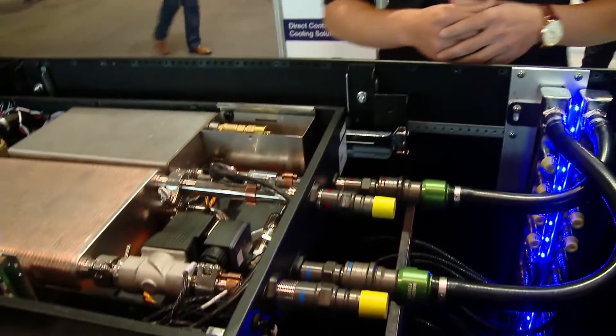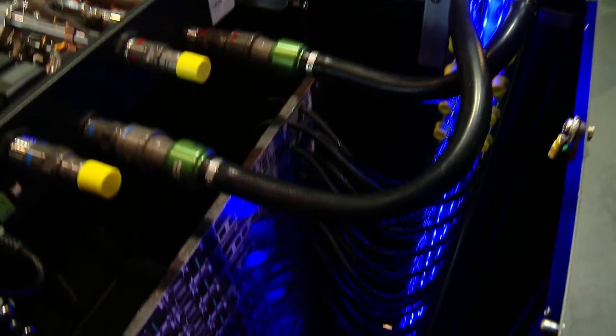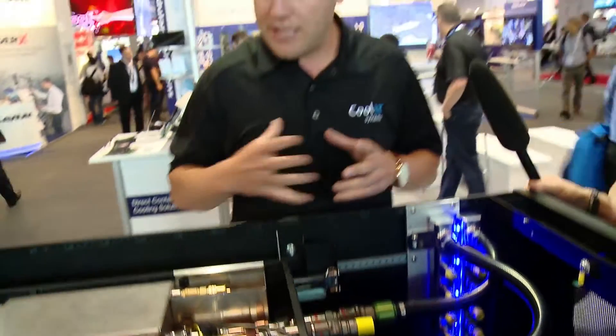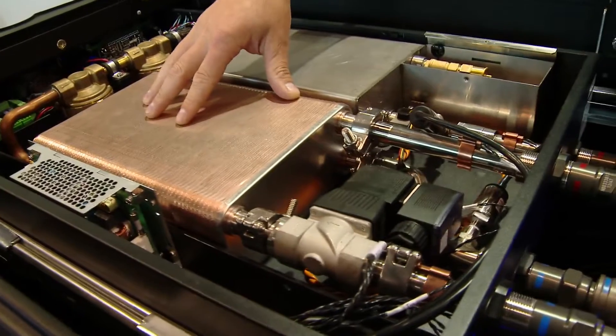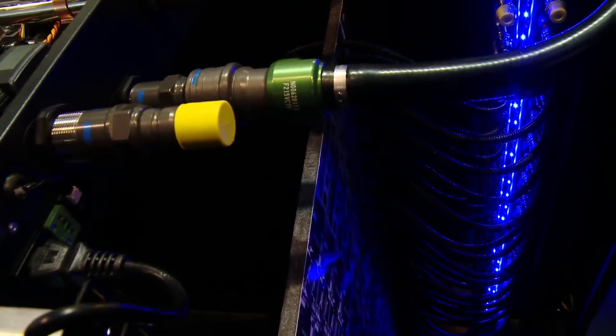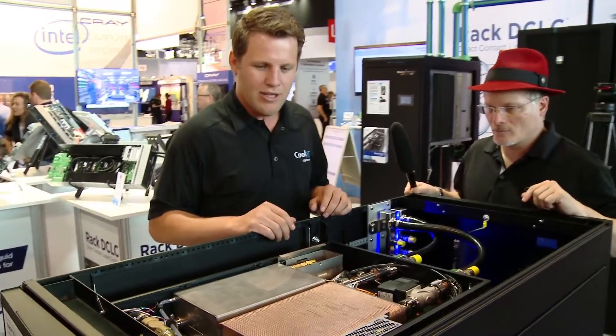We use the AHX more often in a test or beta site. Our most popular product is the CHX40, one of our liquid-to-liquid machines. Once you get all the warm water to the manifold, it connects to the CHX40 with dripless quick connects, and then we exhaust that heat through a liquid-to-liquid heat exchanger using facility water. We have a bunch of functionality inside this system: redundant pumping, dew point calculations to make sure there's no condensation, and full reporting on temperatures, flow, and pressure drop.